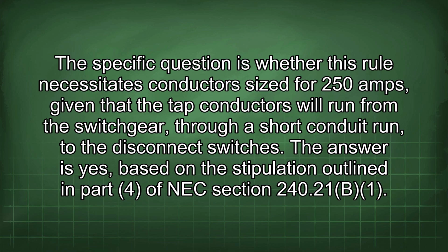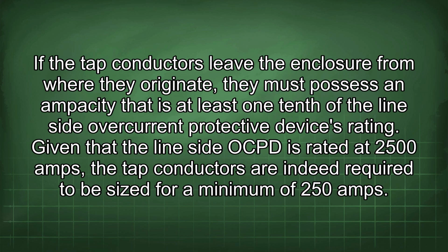The answer is yes, based on the stipulation outlined in Part 4 of NEC Section 240.21(B). If the tap conductors leave the enclosure from where they originate, they must possess an ampacity that is at least 1/10 of the line side overcurrent protective device's rating. Given that the line side OCPD is rated at 2500 amps, the tap conductors are indeed required to be sized for a minimum of 250 amps.